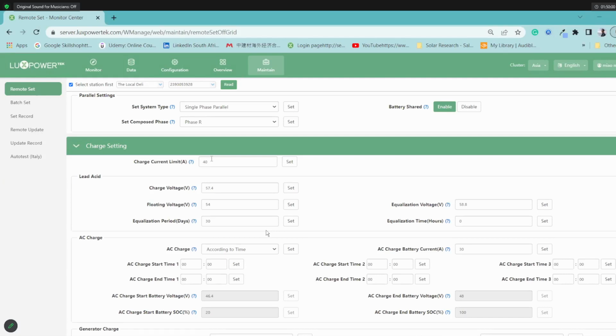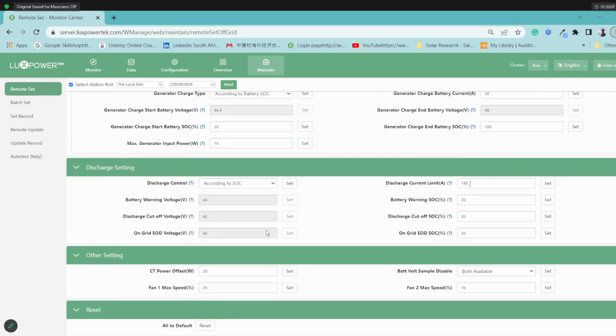Okay, so when you're doing a lithium setup, make sure that you insert the correct charge current limits, including the discharge current limit. That's fine. And then have a look at your AC charge current, you need to also set this accordingly. I'd recommend you just leave it there for now, it's fine.